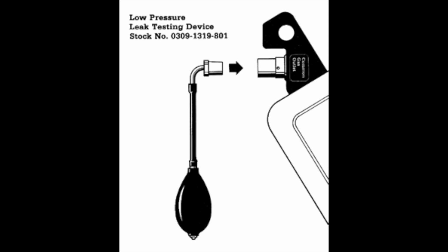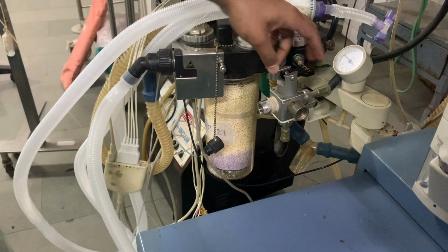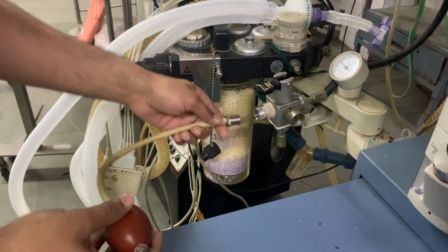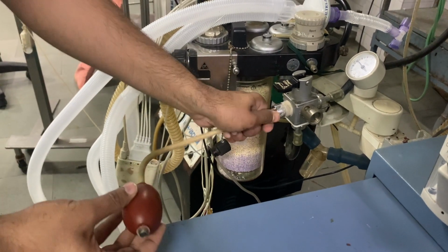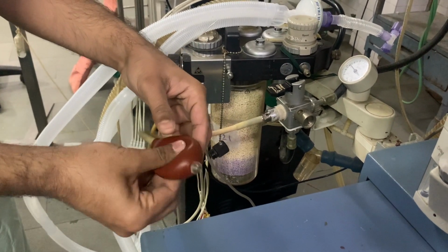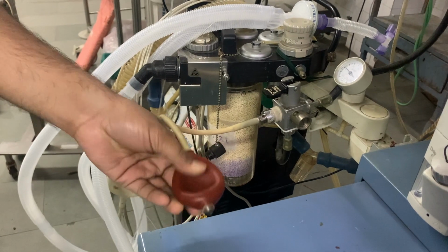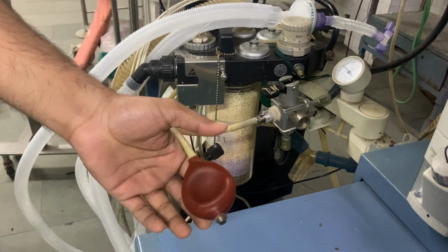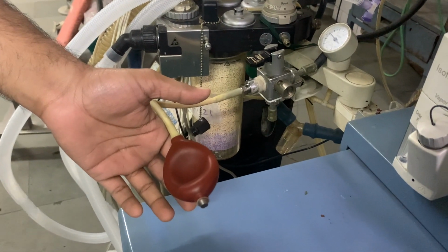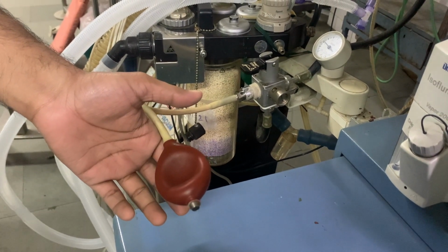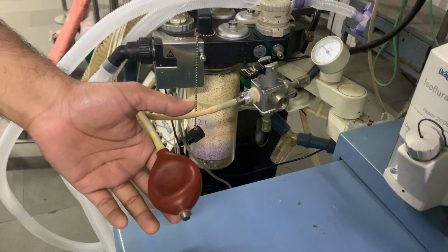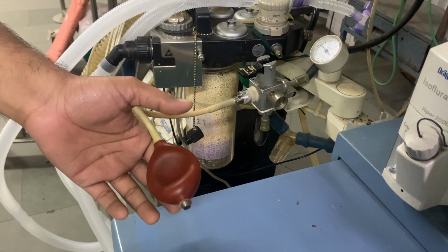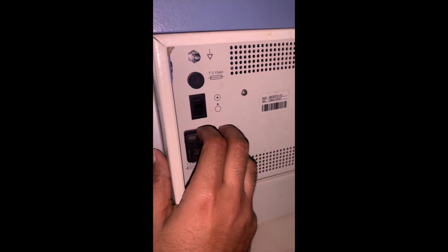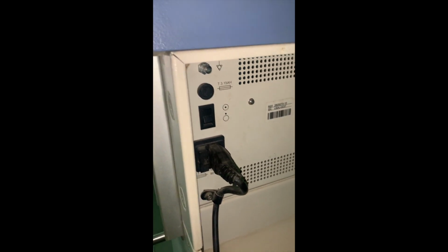Before performing the check, make sure the master switch is off, flow control valves are off and all the vaporizers are off. Attach the suction bulb to the common gas outlet and squeeze it until it's fully collapsed. Verify that it stays in this state for at least 10 seconds. Open the vaporizers one at a time and repeat the same procedure. If the bulb remains collapsed, that means there is no leak in the low pressure system.